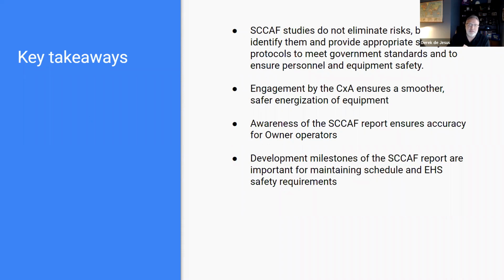Additionally, in the specification for developing a power study, there will be incremental milestones that should be followed. Usually a draft report is issued to ensure we have the right software and the right qualifications of the individual or company developing the report. A second draft should be issued, ensuring we have the proper coordination of all the devices and equipment. Then a final study comes out at the end of the project to capture any changes or challenges, such as equipment feeder lengths that have changed, or breaker model numbers that were replaced. This final study should be tracked in Procore or ACC or whatever tool they're using, to track all of those revisions. The owner then has this file at the end of the day.